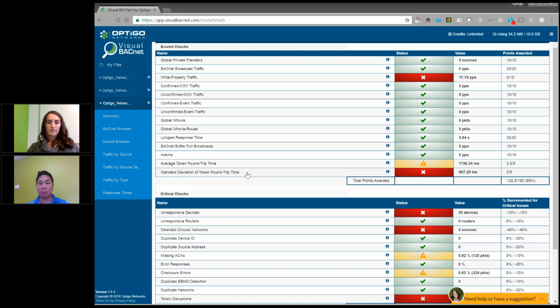But in this case, the standard deviation is very high, which means sometimes the time to go around the loop is very short, sometimes very long. Anything above about 100 milliseconds typically means a token was lost, at least one device lost a token, and that's why it took so long to go around the loop.